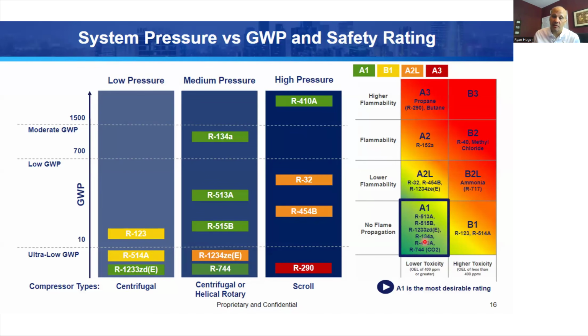We had A's and we had B's, right? A's meant that they were lower toxicity refrigerants. B meant they were higher toxicity refrigerants. Obviously, we'd like to work with lower toxicity stuff when we can. That would be more desirable. Once in a while, you have to do something toxic, like maybe you worked on a big centrifugal with R-123 back in the day, or maybe you worked on an ammonia chiller in an ice rink. Once in a while, we do that stuff. We'd like to stay in the A category where things are non-toxic.